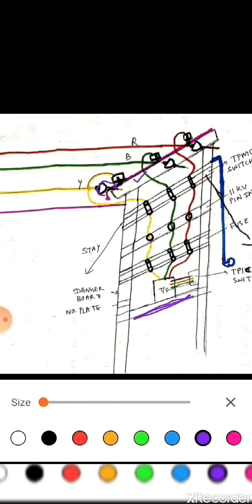Next one is eye bolt. Now eye bolt is required to connect the earth wire with the pole. Here is the earth wire. Earth wire is connected to the pole through the eye bolt. So quantity is 1 number. Next one is dropper angle iron 75 mm into 75 mm into 8 mm into 2.2 meters long. Here is the dropper angle iron. The dropper angle iron is installed to connect the pin type insulators, and the quantity is 1 number.